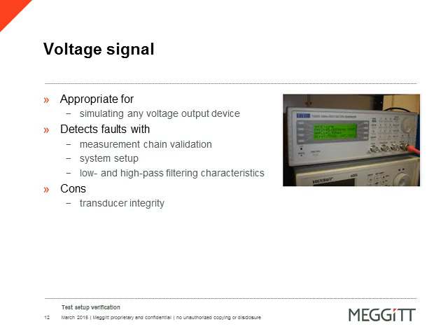voltage signal simulation. Voltage signal simulation is accomplished by introducing a known voltage and known frequency into the system. This signal path verification test is used to prove the entire cabling from the transducer all the way to the data acquisition system. Voltage simulation can be accomplished in many ways, from as simple as connecting a battery to the input leads of the cable, or by using a more complicated and thorough test method with the use of a function generator or handheld signal source.